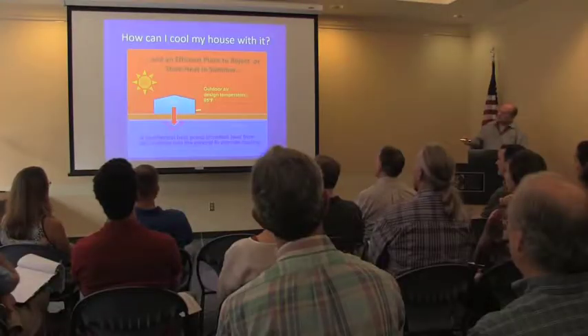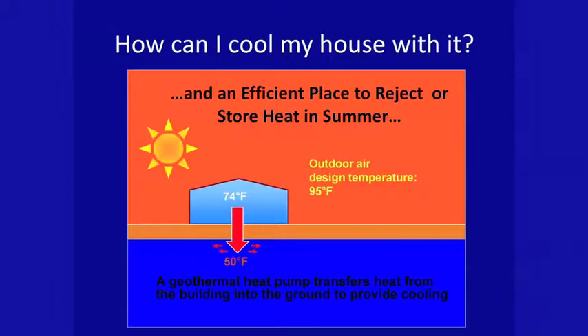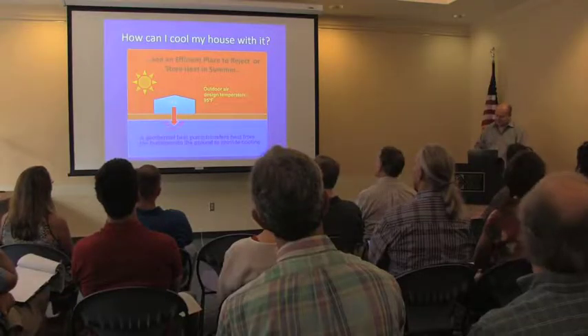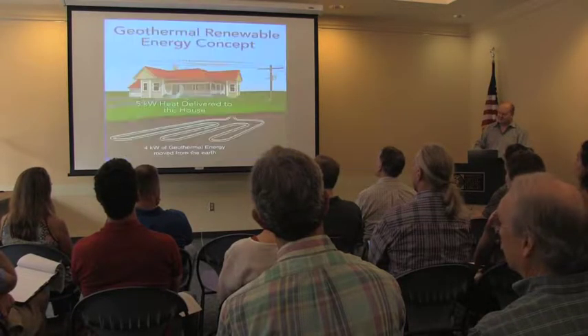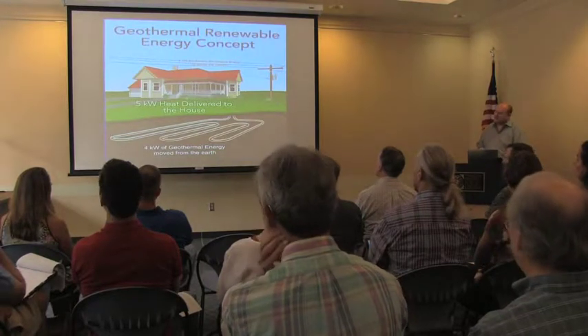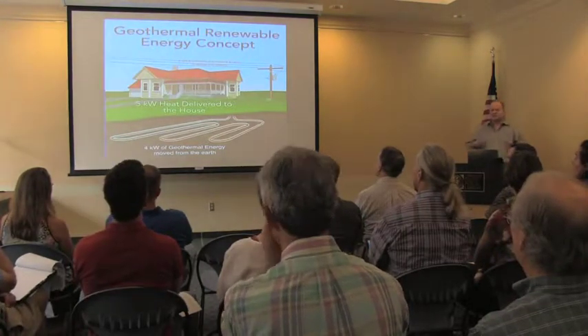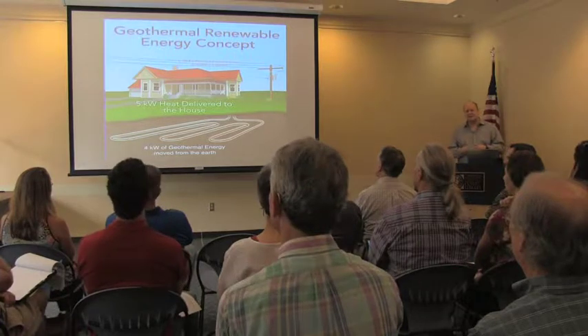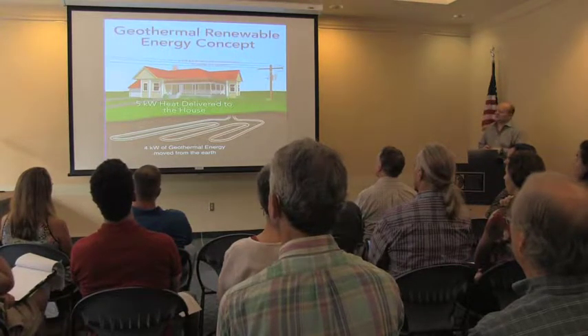Now, the beauty is the heat pumps can go in reverse. You can take the heat from the house and reject it to the ground. And you do that extremely efficiently because you don't reject it against a 95 degree outside temperature, you do that against 50 degree nice and cold ground. And that's where the high efficiencies come in, both heating and cooling. And the trick is you need some energy to do that. You need a compressor to do that. Every heat pump has a compressor in there.